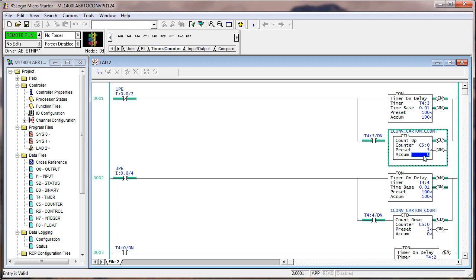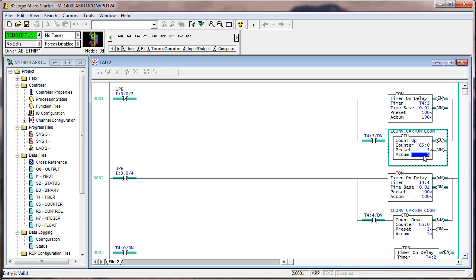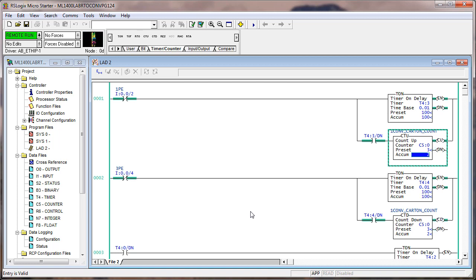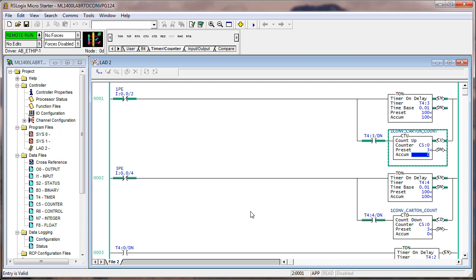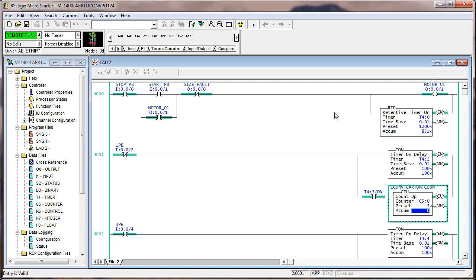3PE, we'll turn that on. Now we've got a carton going off of conveyor one, and when it clears 3PE after one second, then we count it as off. I'm going to count some back on. Okay, I've got three cartons back on conveyor one. Now I'm going to take them off of conveyor one onto two conveyor. The optical path is blocked, but nothing happens until it clears 3PE, and then one second later, it counts it down. So now all three cartons have left one conveyor to wherever they're going. Now we happen to know they went onto two conveyor, and of course they won't go on two conveyor unless two conveyor is running, and two conveyor was not running.